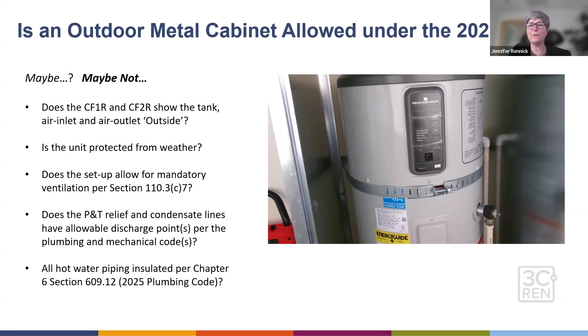Some of the other things we've seen is that the pressure and temperature relief and condensate lines haven't been discharged properly, which might be in violation of certain plumbing and mechanical codes. And a lot of times we've seen the hot water piping isn't insulated. So again, it's possible this would work, but maybe not. This is an FYI for all of you.